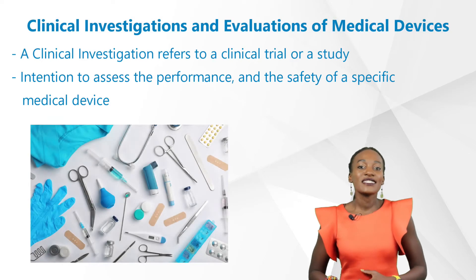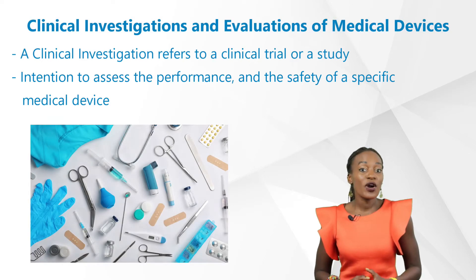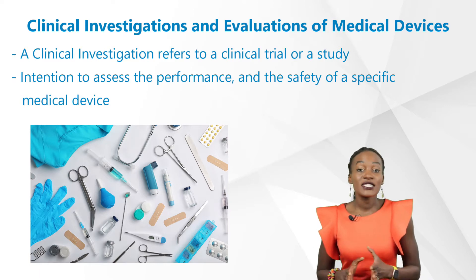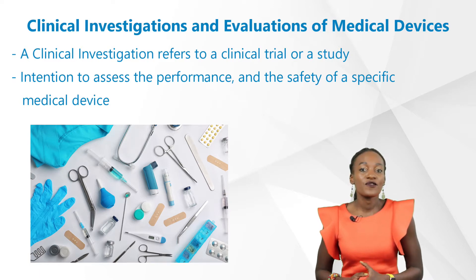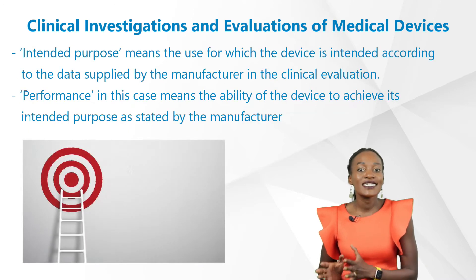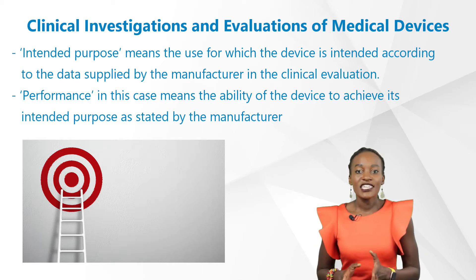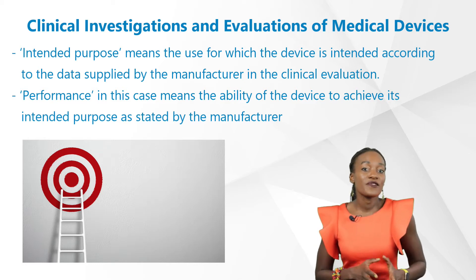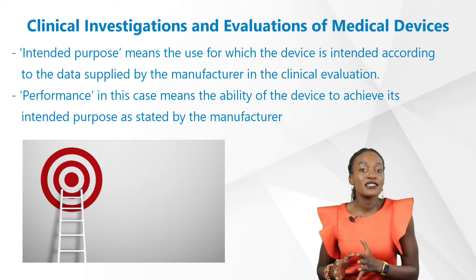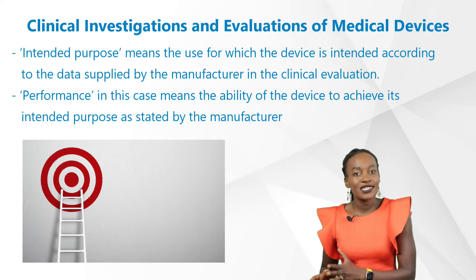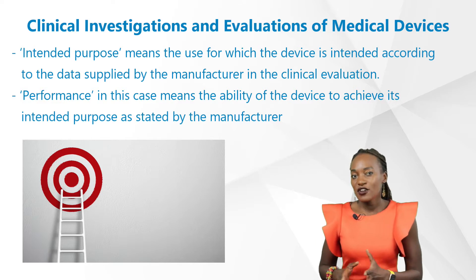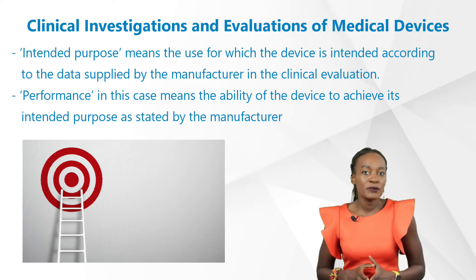A clinical investigation refers to a clinical trial or a study conducted in humans with the intention to assess the performance and the safety of a specific medical device. Pay attention to the keywords: intended purpose, performance, and safety. Intended purpose means the use for which the device is intended according to the data supplied by the manufacturer in the clinical evaluation. Performance means the ability of the device to achieve its intended purpose as stated by the manufacturer.